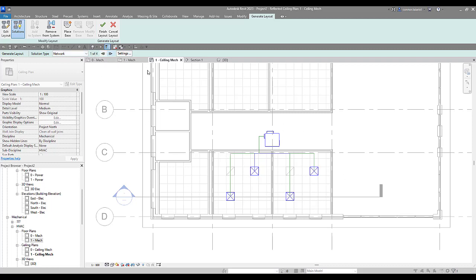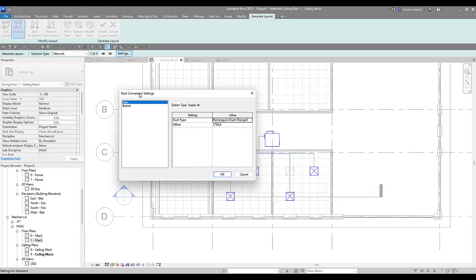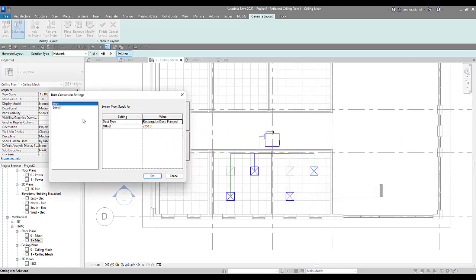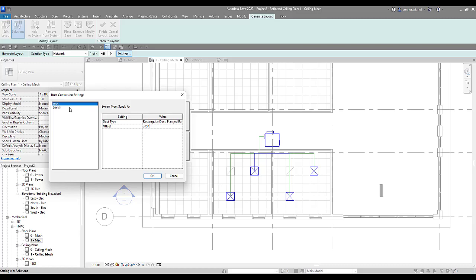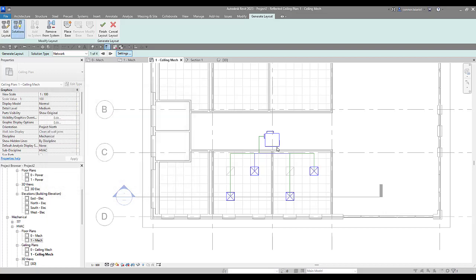Again, still in the options bar, we're looking under settings. This will allow you to confirm the duct type and the offset from the level for the main and the branches. We can change the duct type for our main. We can change the offset. I know my middle elevation here for my VAV is, I believe I set it to 3750. So I'm going to make everything 3750, the offset 3750 from level. I'm going to press OK.